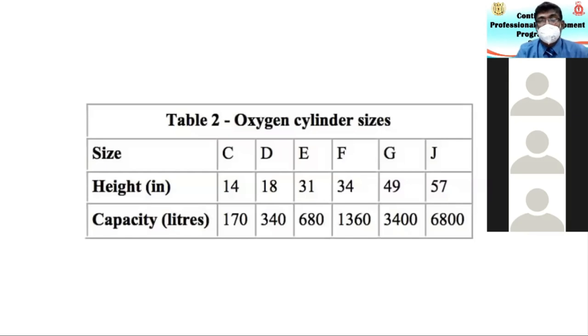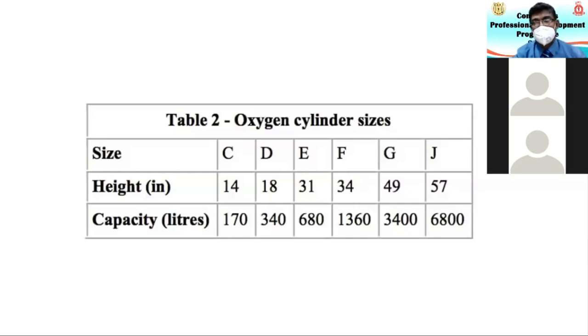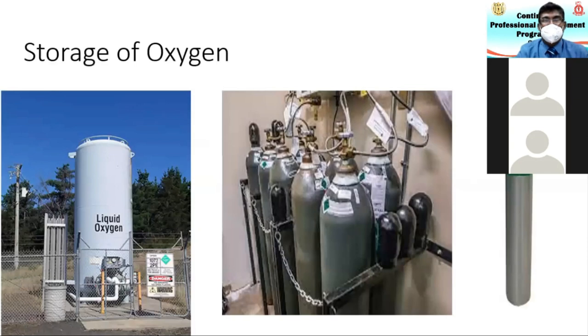Sometimes we use high flow nasal oxygen, which is the most commonly used oxygen device nowadays for COVID. But unfortunately, it uses a lot of oxygen. If you use this J cylinder for high flow nasal oxygen at about 60 liters per minute, if you calculate, this cylinder is only enough for a couple of hours, about 110 minutes. So this is the solution for that problem.